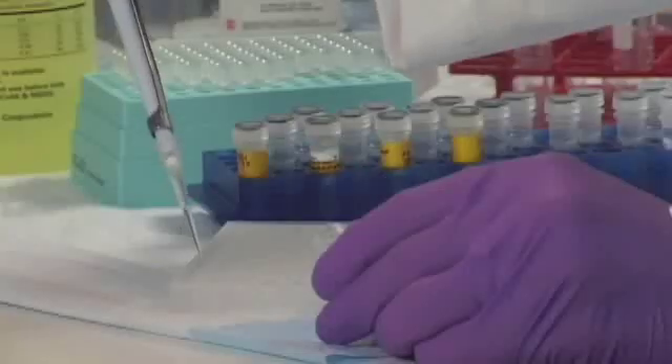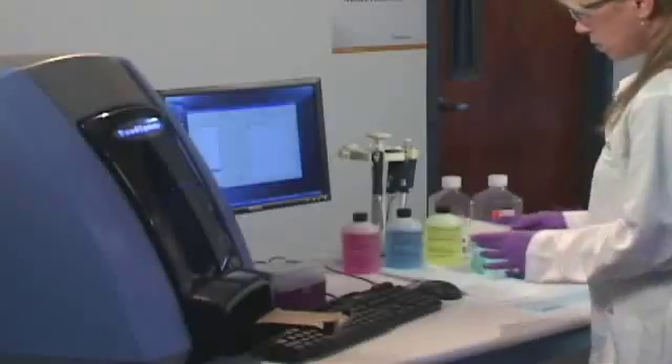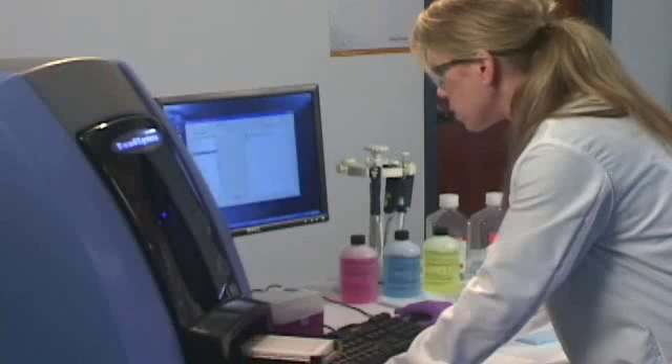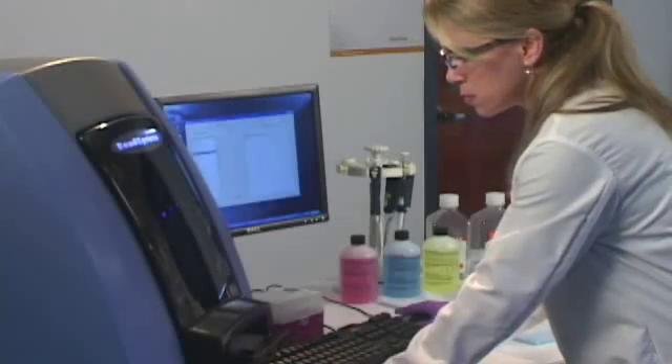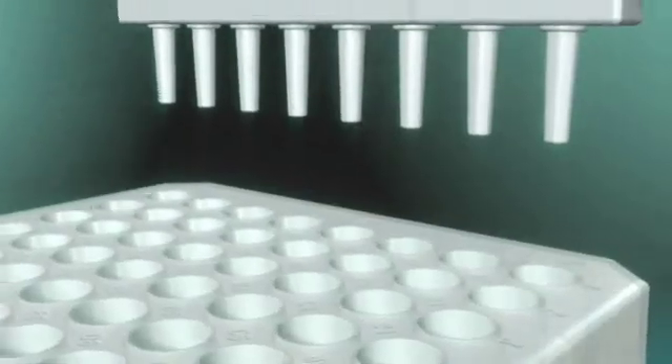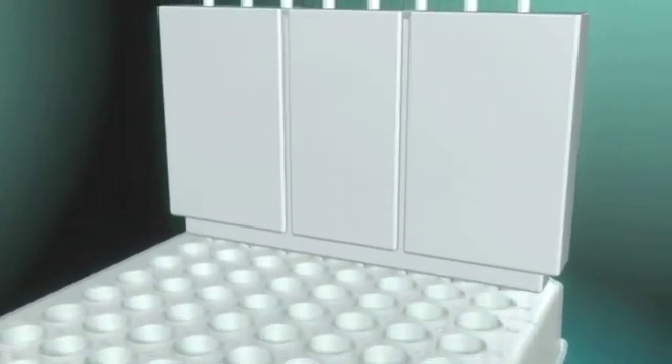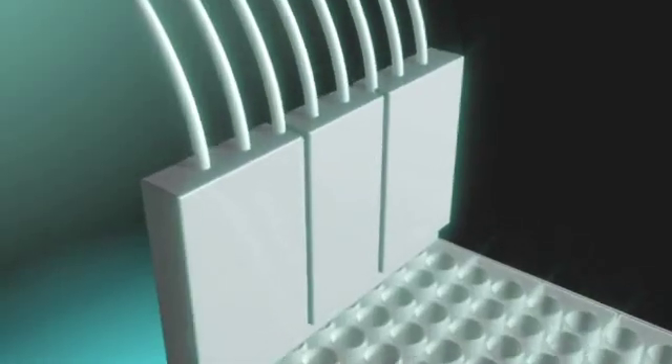Assays developed with Veracode beads are analyzed with the BeadXpress Reader, a high-throughput detection scanner. The fluidic system in the BeadXpress Reader draws eight samples from the microplate at a time, and Veracode beads from each sample are delivered into sectors of the system read cell.